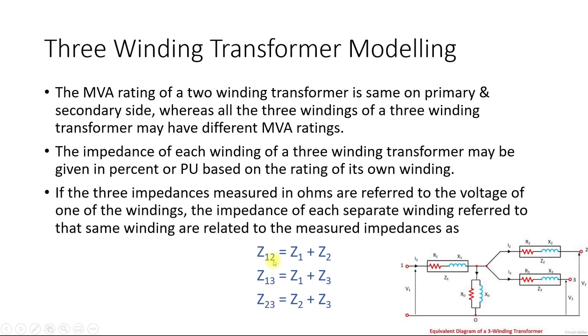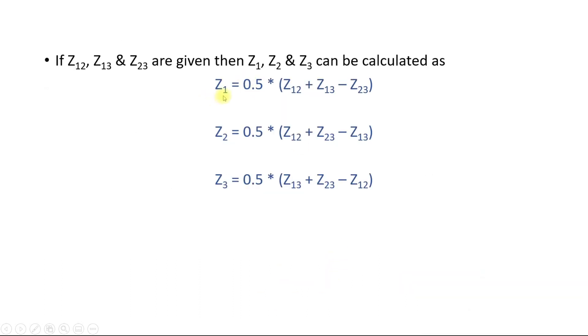Z12 can also be known as Zhl (HV to LV), Z13 as HV to tertiary voltage, and Z23 as LV to tertiary voltage. If you are given Z12, Z13, and Z23, you can convert them back to Z1, Z2, and Z3 using: Z1 = (Z12 + Z13 − Z23) / 2. This works because Z1 appears in both Z12 and Z13 (twice total), while Z23 does not include Z1, so subtracting Z23 and dividing by 2 isolates Z1. This way you can calculate all individual transformer impedances.